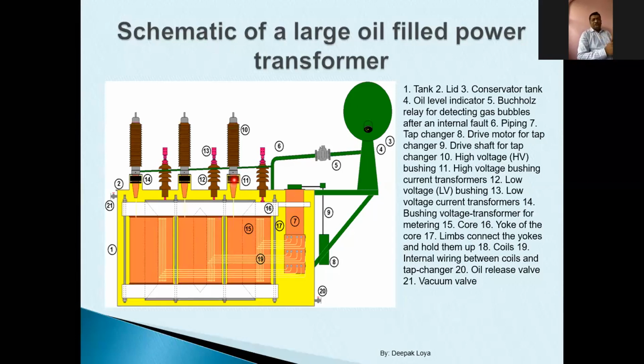So I will show how the core looks like. There is a yoke, nothing but the part of core itself, the top part of the core. Then there will be some clampings required because there will be electromagnetic forces acting on my transformer. To prevent the movement of my transformer active part because of these forces, we have to clamp them together. There will be windings, LV winding and HV winding.